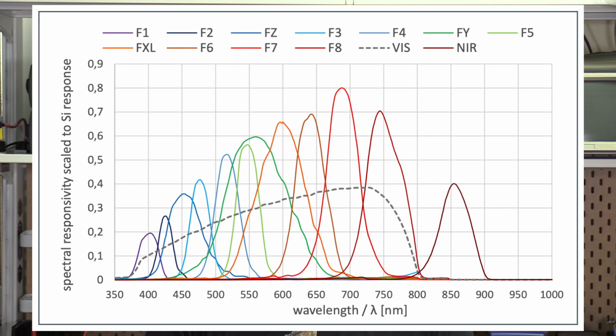The problem is the elements of this sensor do not exactly match what the densitometer ISO spec calls red, green, and blue. They're kind of their own distribution. And so being able to get readings from this device that actually match your standard color off-the-shelf densitometer is far easier said than done. It's no longer just a matter of calibrating the density range. I also need to calibrate the spectral sensitivity of the light sensor in the device. And that's a very complicated problem. The data sheets and application notes for the sensor don't give a lot of good detail on how to do it correctly. They just drop a couple of keywords and hand wave it.